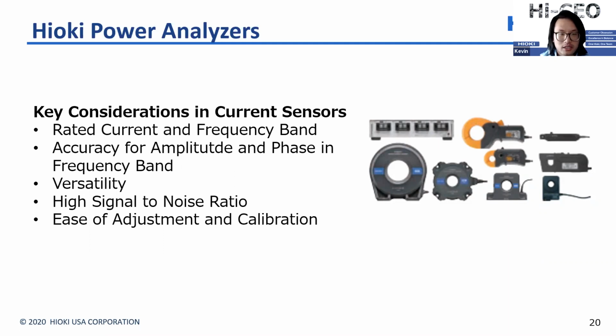Our sensors combine the flux gate method as well as the current transformer method. The flux gate method allows the detection of DC current and doesn't require the use of semiconductors, giving us the advantage of temperature stability and a low offset voltage. So we are also able to offer sensors with a 0.02% accuracy and a band of 3.5 megahertz. Our sensors are also able to operate between negative 40 degrees C all the way up to 85 degrees C.